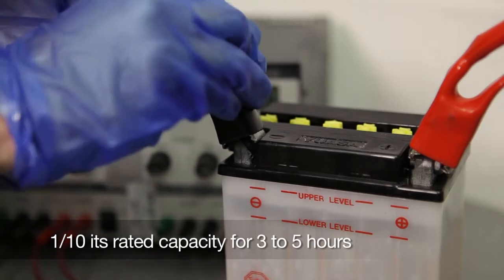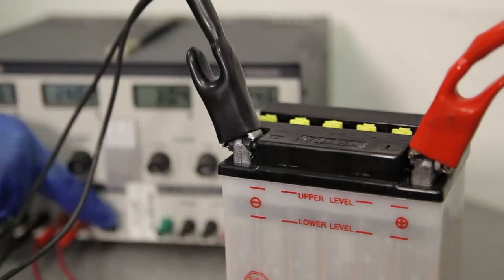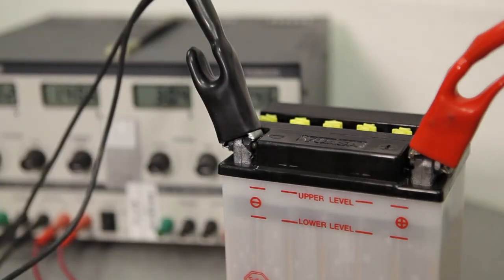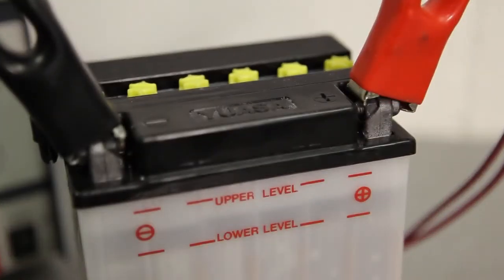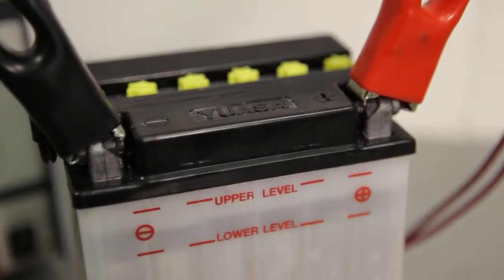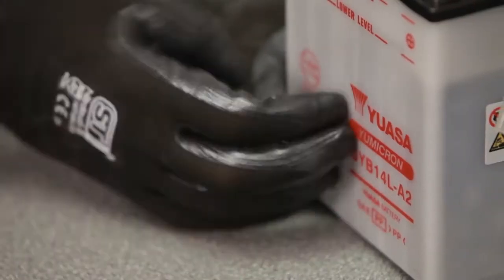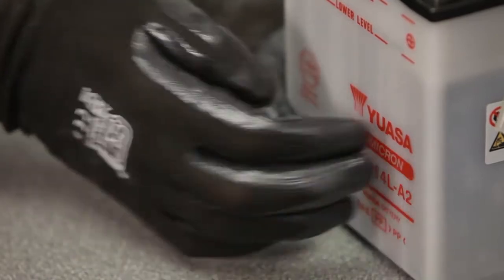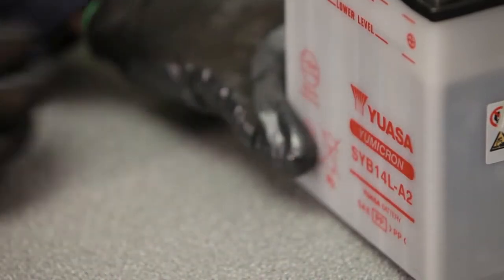Do not connect or disconnect the charger to the battery while the charger is switched on, as this may cause sparks that could ignite the hydrogen gas emitted from the cells during charging. Monitor the electrolyte level during charging and top up to the fill line as necessary.